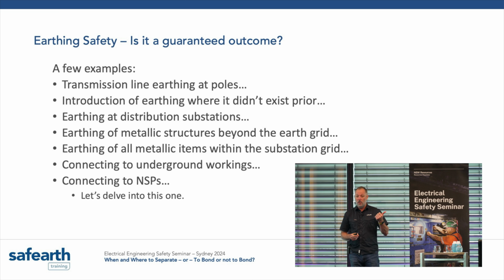You could unearth the pole completely, but that creates some issues with insulation. But you can absolutely design the earthing system there so that you don't have to go and touch the low voltage asset, you don't have to do anything different to what the farmer has, and you can really control it very well.